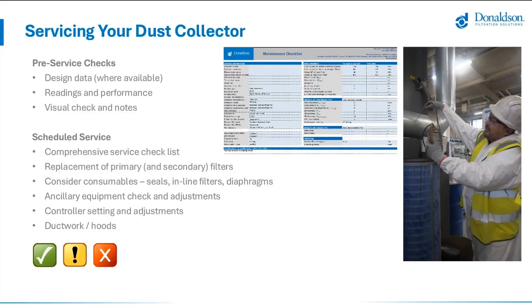The service itself needs to be supported by a comprehensive and detailed service checklist. All components need to be checked, recorded, adjusted as required, and sometimes replaced. Often a collector service can be viewed as just replacing the filters, but this is not the case. Ancillary components need to be checked, consumable items replaced, controllers checked and reset as required, and beyond the collector itself, ductwork, safety devices, and mechanical discharge items need to be checked and serviced.